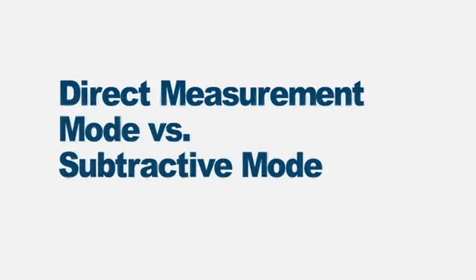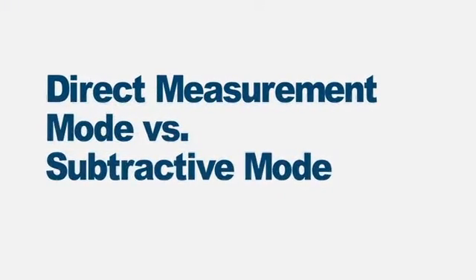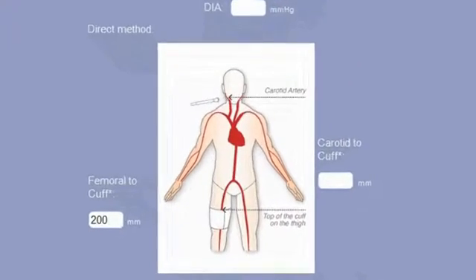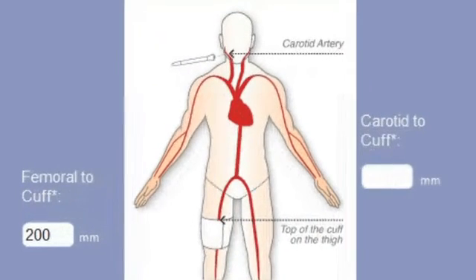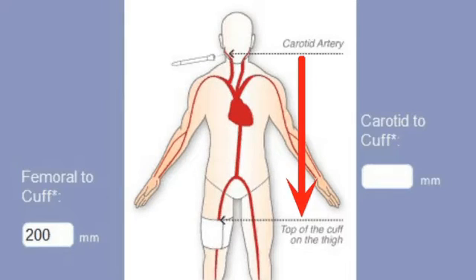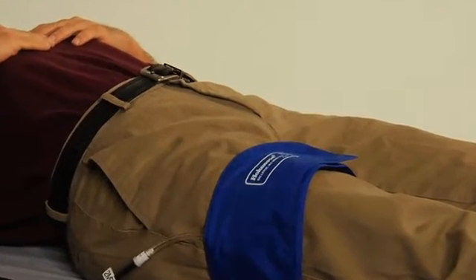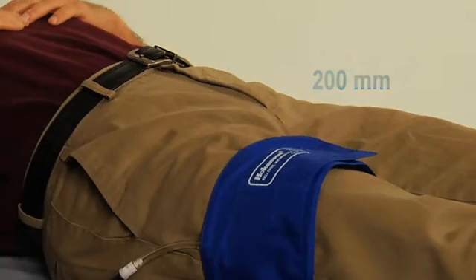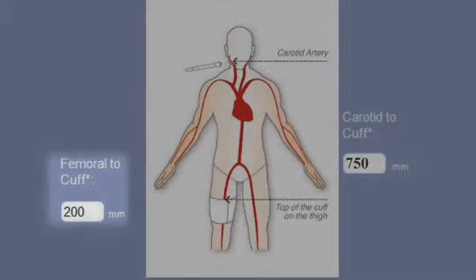Distances can be entered in one of two modes. Using the direct measurement mode, the distance is measured directly from the point of the strongest carotid pulse to the top of the femoral cuff. This value is entered in the box marked Carotid to Cuff. The system default distance from the femoral artery to the edge of the cuff is 200 millimeters; the actual distance should be measured for each patient and entered into the system.